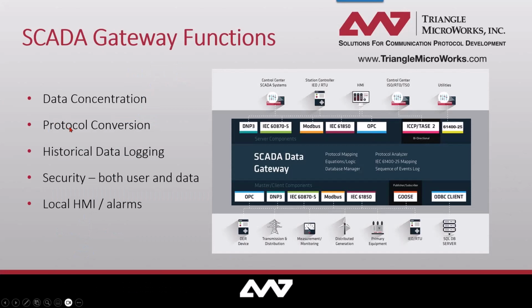There's also protocol conversion. This is a feature that is where our gateway originally started out. And what it will allow you to do is translate between protocols. So, for example, we could have a hypothetical substation that included both 61850 and Modbus RTUs monitoring the electrical equipment. But if your control station is expecting IEC 60870-5-104 traffic, there's obviously a mismatch there. So another thing a gateway could do is take the data from your Modbus and 61850 devices, go through the mapping logic, and map that to a database for the control center, the SCADA Master, to see. So not only do you map the protocol, but you can map the like types. So obviously, very simple example would be a 61850 Boolean probably would get mapped to the similar Boolean type in the 60870-5-104.